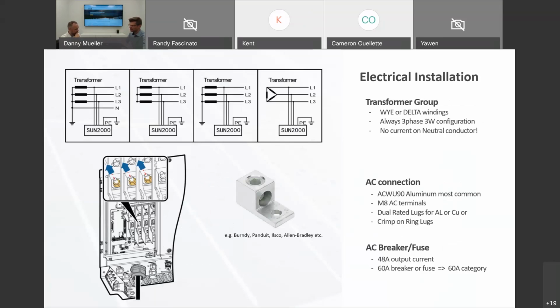When we jump into the electrical installation, the Huawei 45 KTL uses a three-phase, three-wire connection, which means it's not a neutral-based topology. The inverter can use a transformer which has a secondary as a delta or a Y configuration, so you're not tied to one over the other. You can pretty much connect to whatever transformer configuration on the secondary side you have.